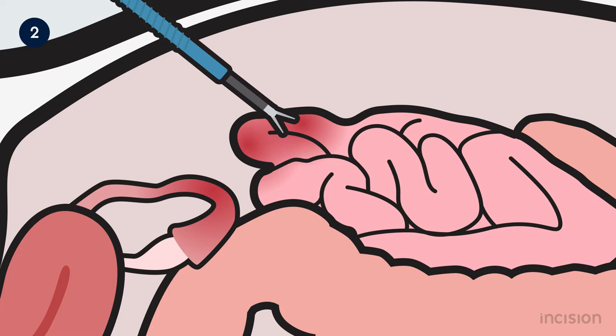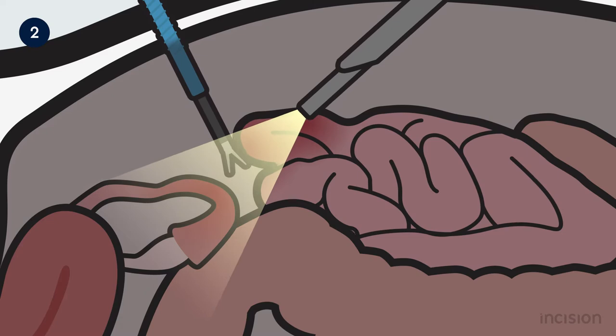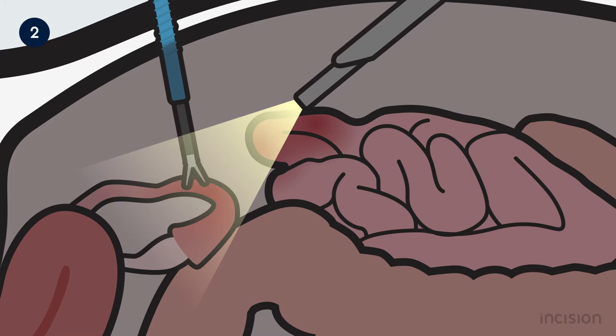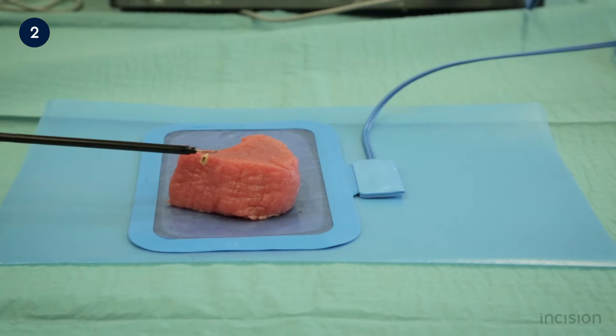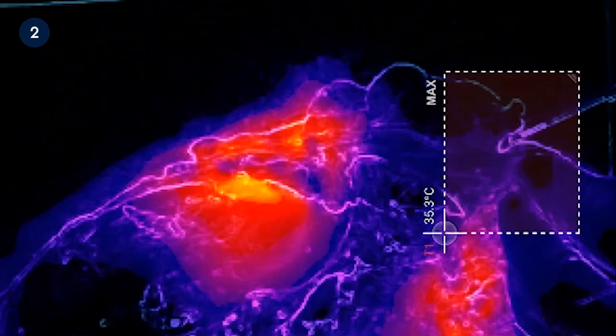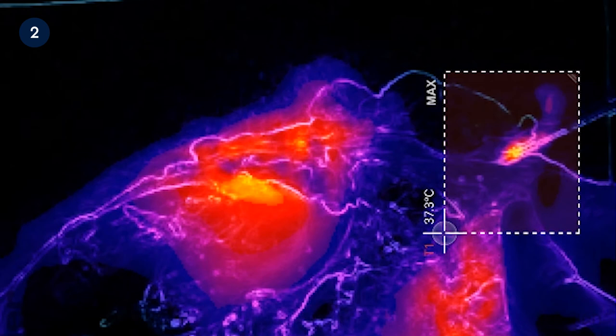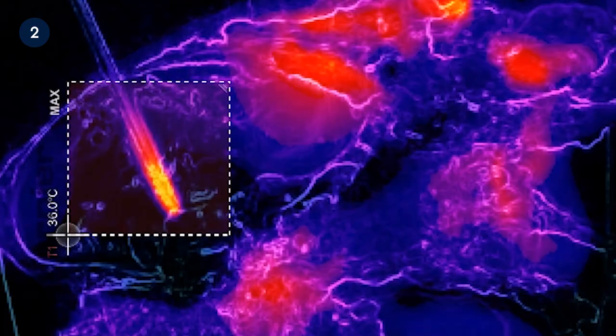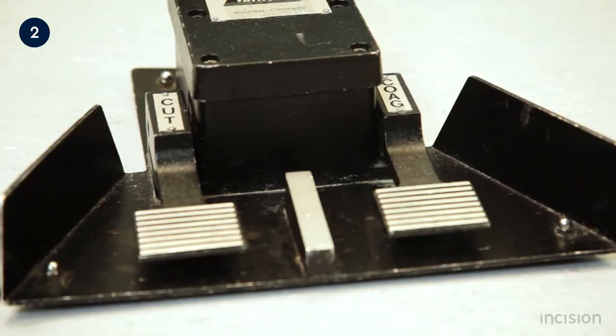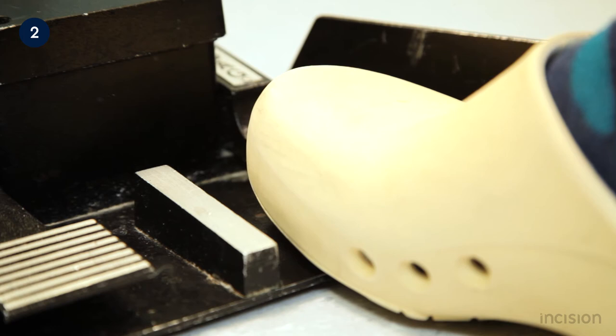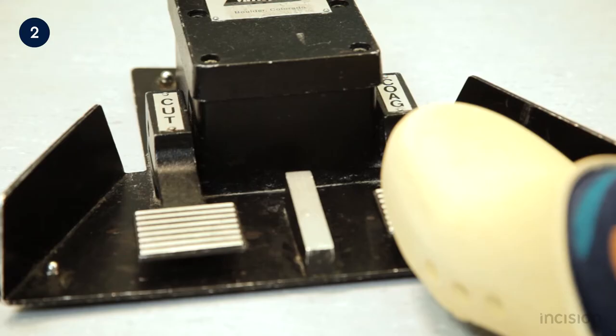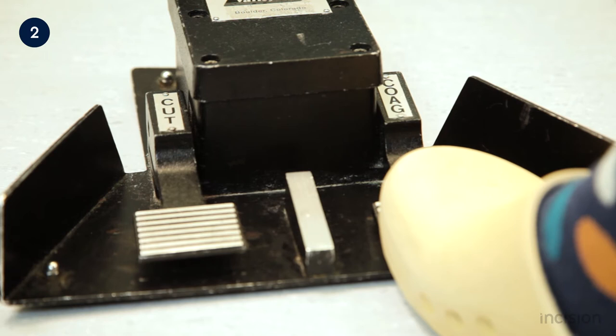To reduce the chance of accidental tip-to-tissue contact, the generator should only be activated when there are no unintended tissues in the proximity of the tip. In addition, the tip should not be in contact with tissues shortly after activation, as the residual heat of the electrode can cause the tissues to burn and stick to the tip. To prevent excessive residual heat, prolonged activation of the electrode is to be avoided. Instead, the use of brief, intermittent activation is recommended.